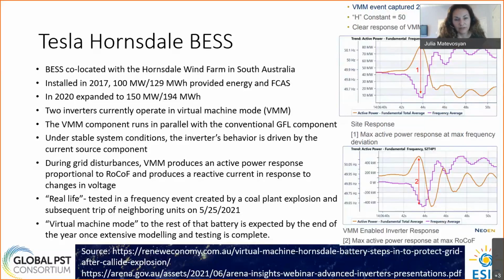This one was recently real-life tested in a frequency event created by a coal plant explosion and then subsequent trip of neighboring units. So there was a frequency event at the end of May. What you can see on the right-hand side in purple is the frequency trace, and in red, the response. On the upper plot, what you can see is the response of the entire plant, and it still looks like fast frequency response proportional to frequency deviation.